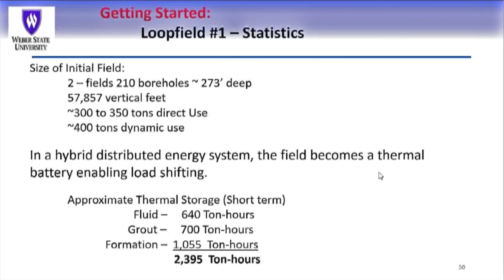When we started looking at the bore field statistics, the ton-hours and so on, my upper field right now has about 2,395 ton-hours, and the lower field has about 2,500 ton-hours. That's stuff we're already starting to build up. We only have two loop fields across the whole campus.